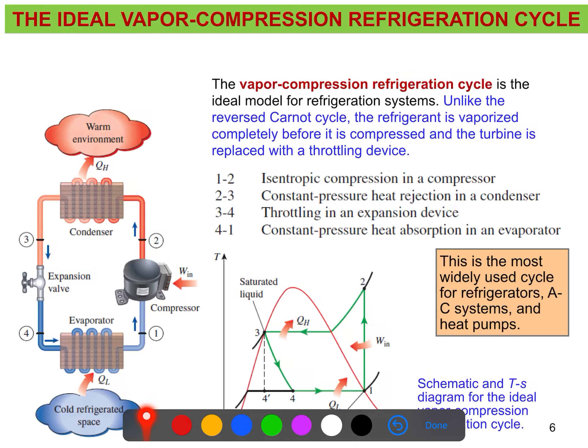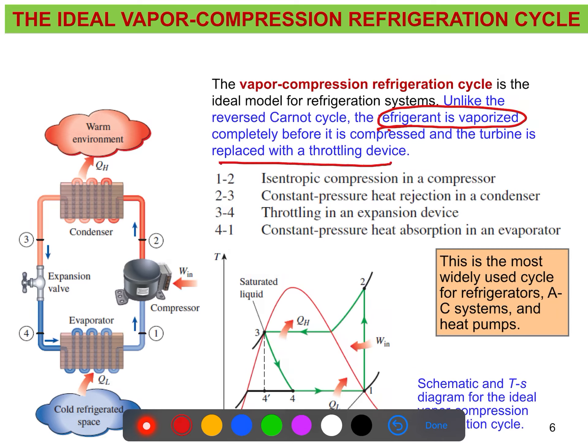The reverse Carnot cycle has some impracticalities, and we can eliminate those by two modifications: first, we completely vaporize the refrigerant — the working fluid — before it enters the compressor; and second, we replace the turbine with a throttling device, such as an expansion valve or capillary tube.